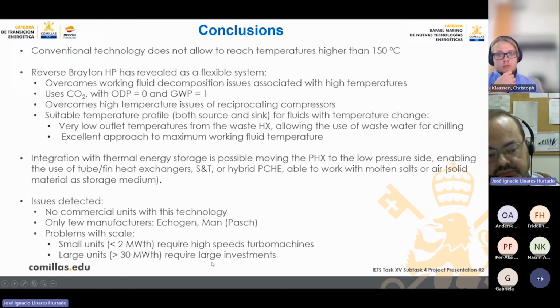For instance, for the heat pump of 70 thermal megawatts we have presented, the turbomachines speed is 6,000 rpm. This is a usual, conventional speed, but with very small machines of this size, we move to 30,000, 70,000, and something like this. So here there is a problem that should be overcome if there is interest from manufacturers to move from gas turbines to this sector. Not now, but perhaps in the future.